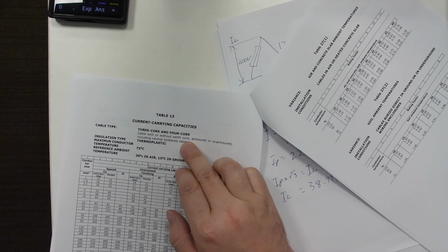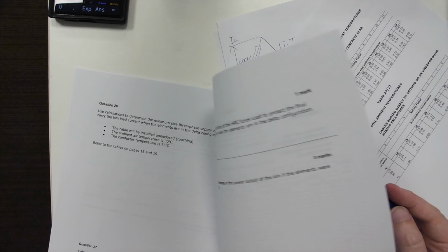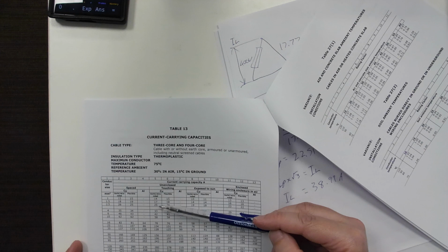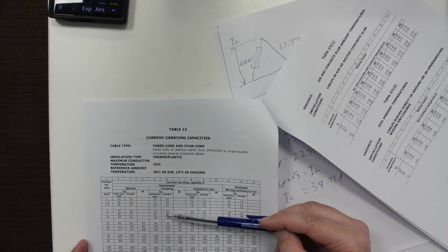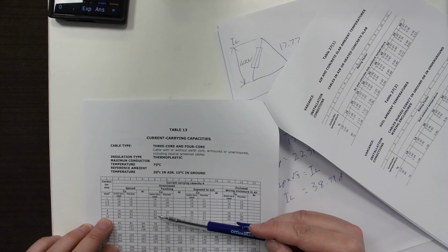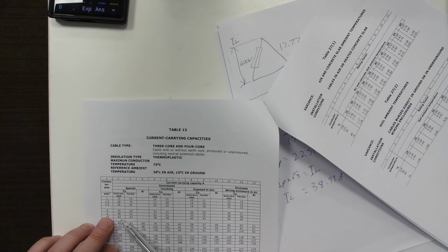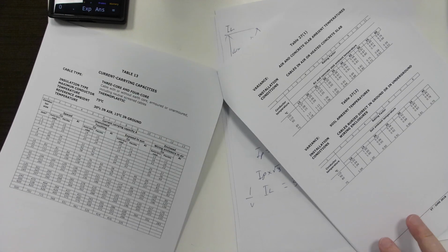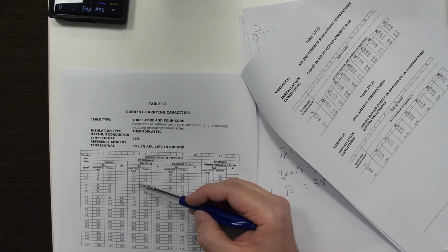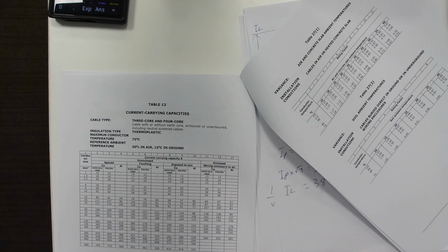This is 3 or 4 core, this is 3 core, and we're unenclosed touching, so that puts us in this column here. We look at stranded, solid or flexible, doesn't really matter too much. We need to be over our 40 amps, and either way we get there with a 6 mil. Because we just follow down this list, we need a value that's bigger than 40. 33 and 32 are not big enough, 42 and 41 are, so 6 millimeter square cable.